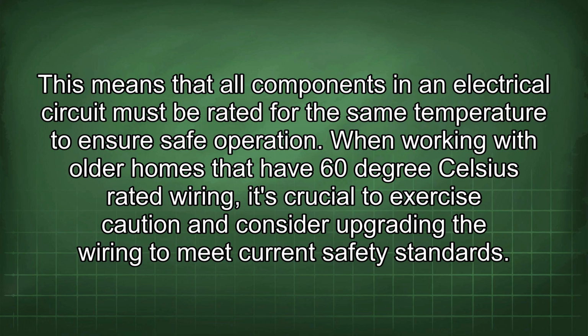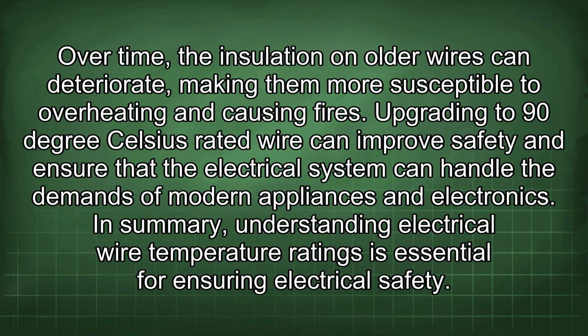When working with older homes that have 60 degrees Celsius rated wiring, it's crucial to exercise caution and consider upgrading the wiring to meet current safety standards. Over time, the insulation on older wires can deteriorate, making them more susceptible to overheating and causing fires. Upgrading to 90 degrees Celsius rated wire can improve safety and ensure that the electrical system can handle the demands of modern appliances and electronics.